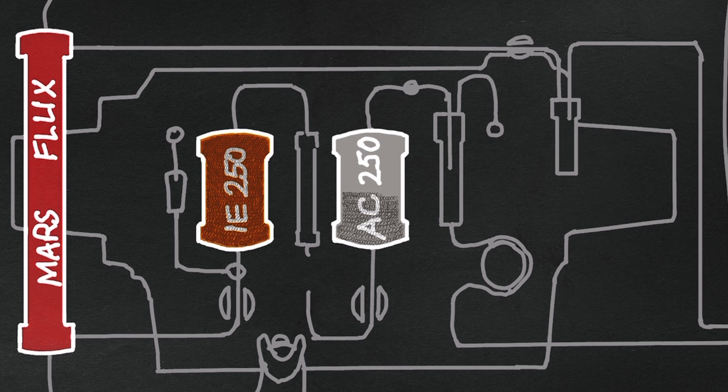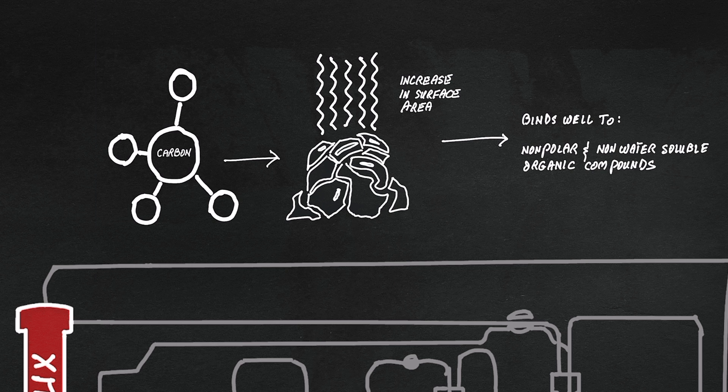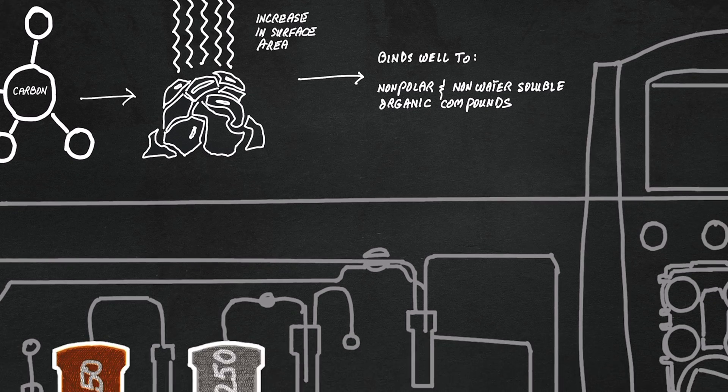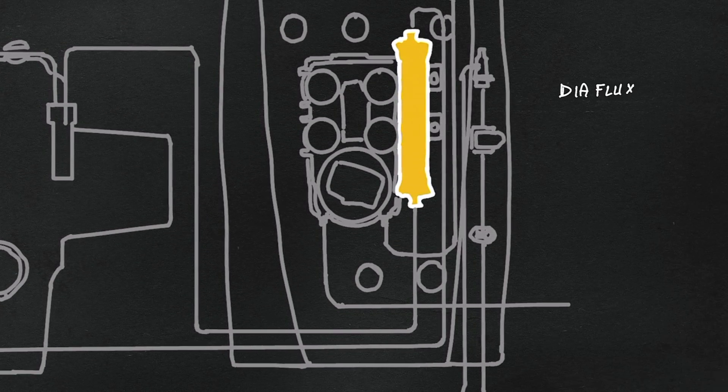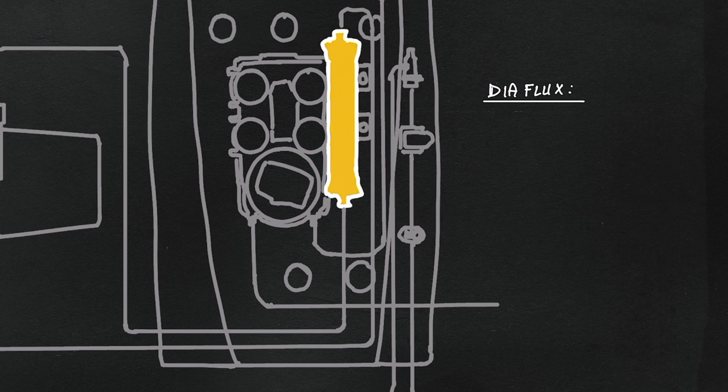The charcoal filter is activated carbon material, which binds well to non-polar and non-water-soluble organic compounds. The last filter is a low-flux dialysis filter with regular-sized surface area, good for small non-protein bound solutes.